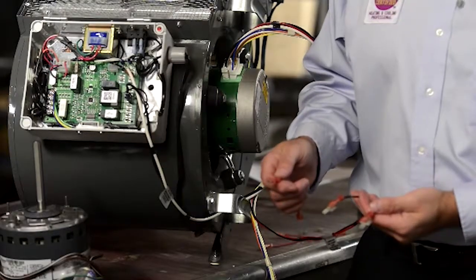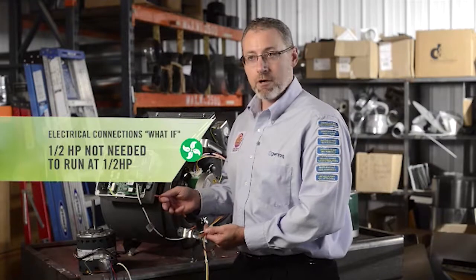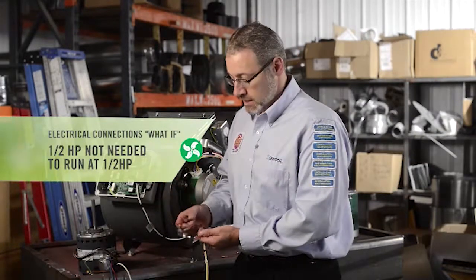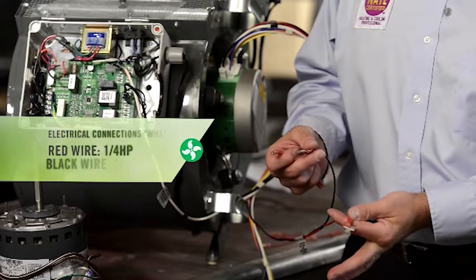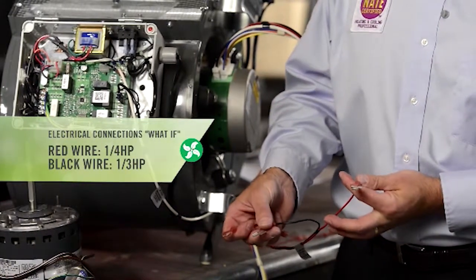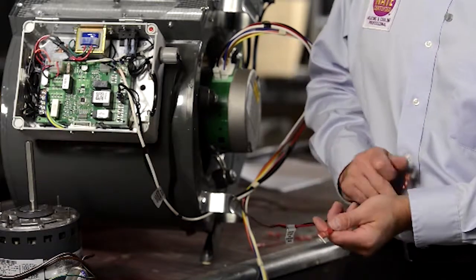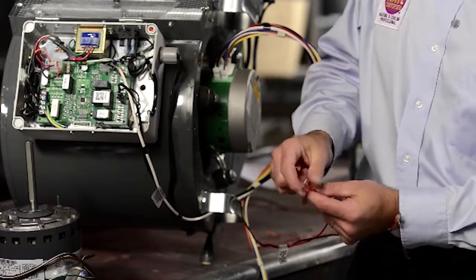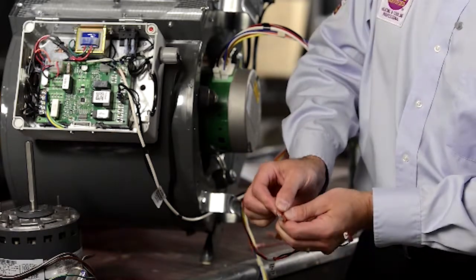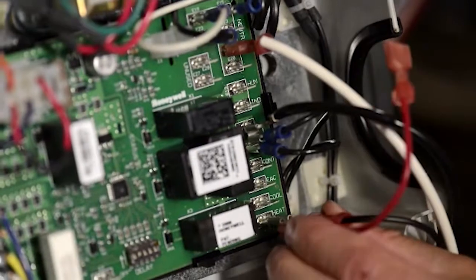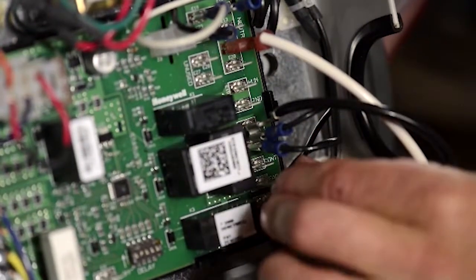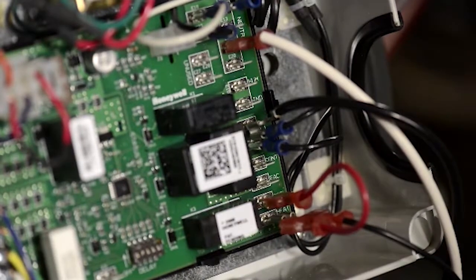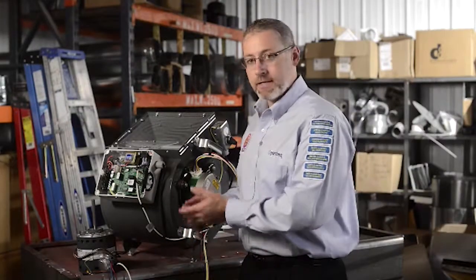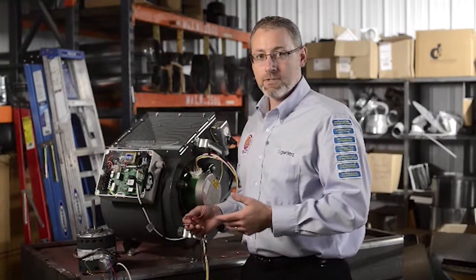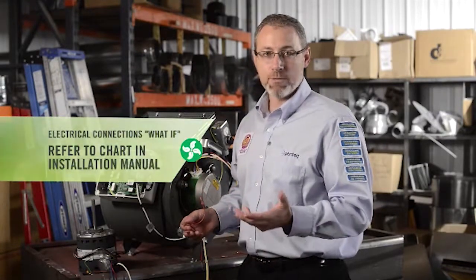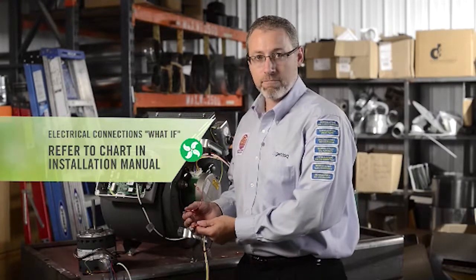The last scenario would be simply to talk about what if you don't need the 1/2 horsepower motor to run at 1/2 horse. You would then either use your red wire for the 1/4 horse application or your black wire for the 1/3 horsepower application. Let's say I needed to use the red wire only, because either one, right? I would take the jumper, connect it to the red wire, and put those 2 wires on my heat and cool terminals. Could have just as easily done that with the black wire. So what this means is it's probably going to take just as long to connect these connections to the HVAC system as it is to open up the manual and look at the chart and determine which horsepower you need and how you're going to configure them with a jumper wire.